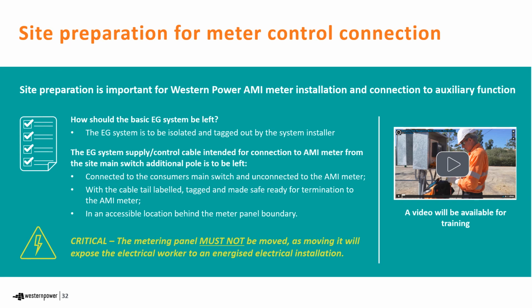You'll need to put an insulating connector on the end of it to make sure it's safe and doesn't touch live parts. And it's just going to be left behind the meter boundary panel. In all this, it's critical that the installer does not move the metering panel, as moving it will expose the electrical worker to an energized electrical installation. A video will now be played and will continue to be available for training later.